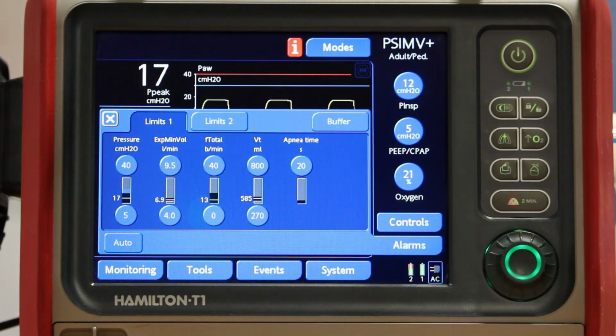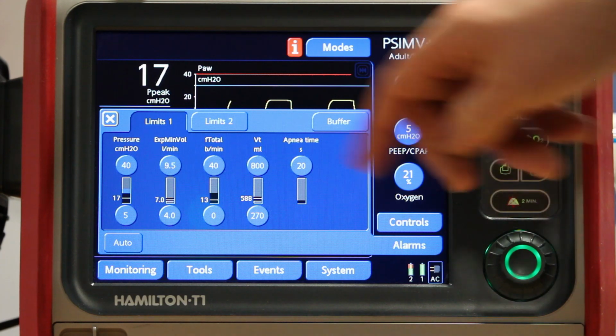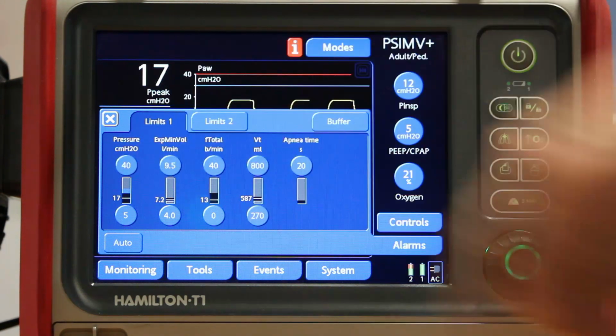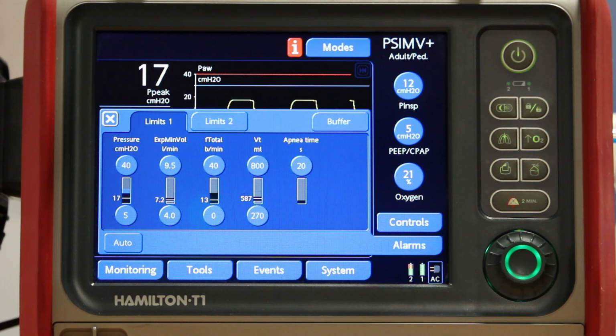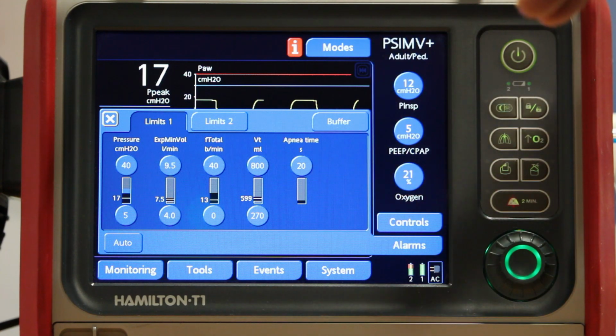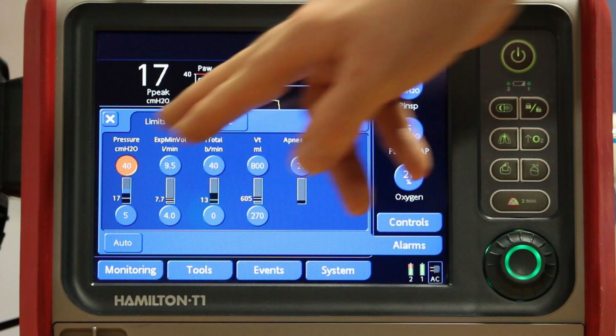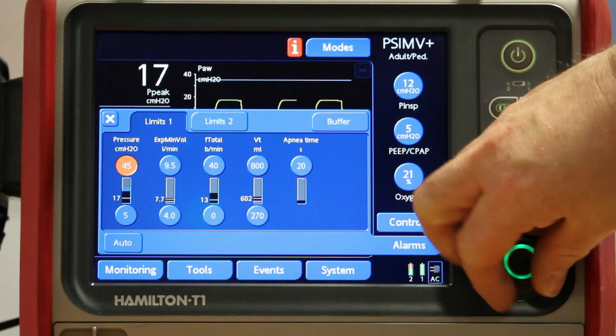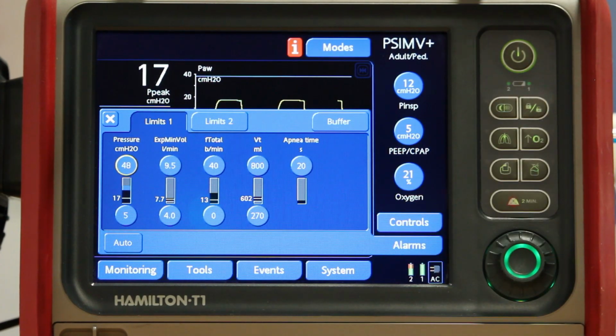Alarms is where I can manually adjust any of the alarms if I know why something is alarming. There is a Pmax default: all Hamilton modes default to a Pmax of 40 centimetres of water. There is a restriction 10 centimetres of water below the Pmax. So if you have airway pressures rising up to the 30s, the vent will start to restrict the breaths or the pressures. If you want to have airway pressures up into the 30s, all you do is dial up your Pmax. So if I dial my Pmax up to 45, my restriction lifts to 35. If I dial it up to 48, my restriction lifts to 38, and so on. So that is the Pmax with the restriction. It's the only alarm that has a restriction associated.